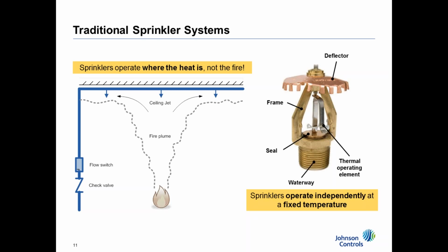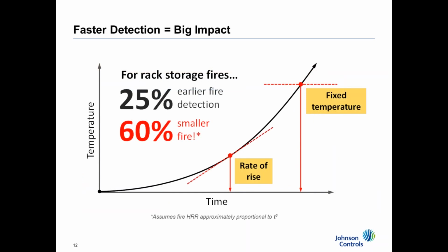So we're trying to work on, and we have worked on, creating an application where we can detect that fire sooner through electronics and be more accurate with what we're doing. The reason that's important is because the faster you can detect a fire, the bigger the impact you're going to have on it. If you can catch it at an earlier rate, you're more than likely going to have a 60% smaller fire through earlier detection, as opposed to a thermal fixed temperature sensor. If you can pick up that rate of rise temperature change across that area, you're going to be able to detect that change very quickly, thus activating the heads that you want to, extinguishing that fire before it gets extremely large.